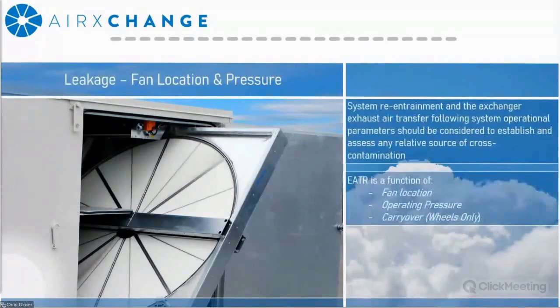So it's important to identify the fan locations and any possible source of reentrainment, as this is going to be used to determine the source of recirculation. And keep in mind that EATR in an energy recovery device is a function of fan location, which ultimately determines your operating pressures. And with a wheel, you're going to have a small amount of air that gets carried over, pumped from one airstream to the other as well.